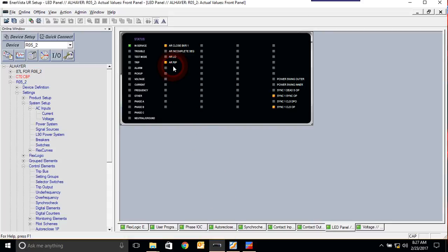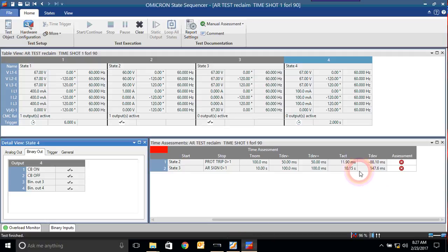Progress again waiting. Now sync operated, see sync operated here. Now sync operated and go to lockout. Okay. Go to the time, check the time, now here 10.15 seconds.